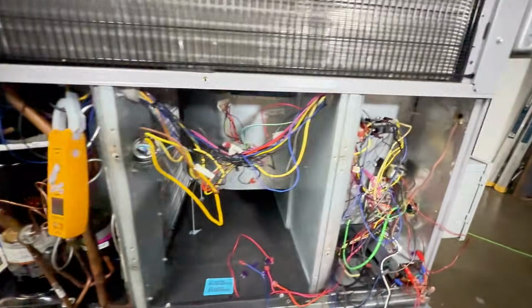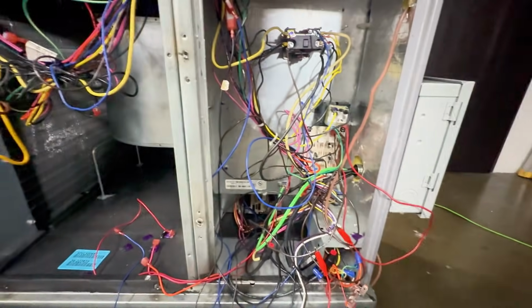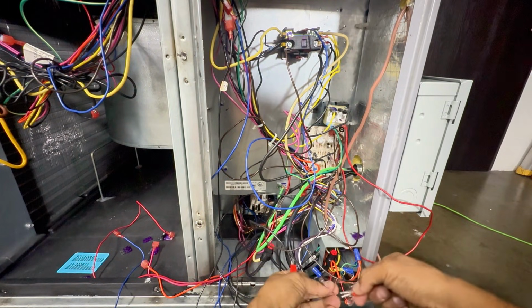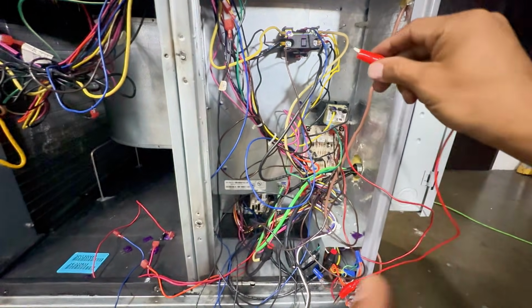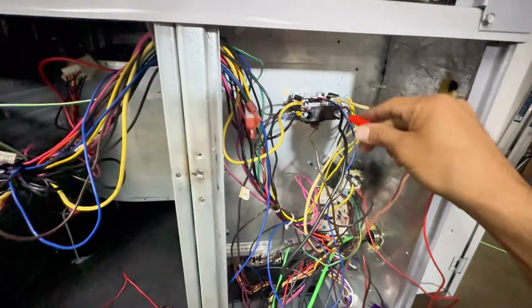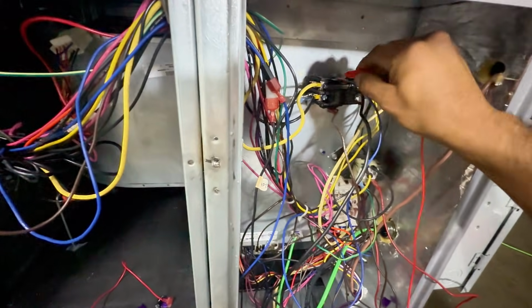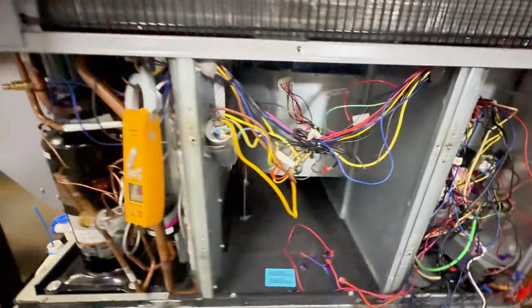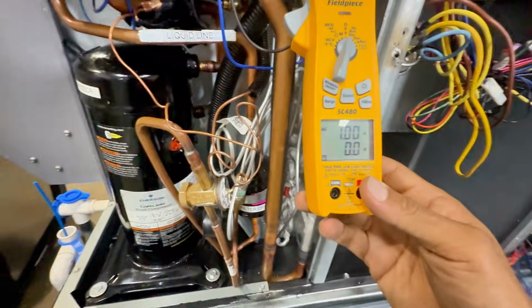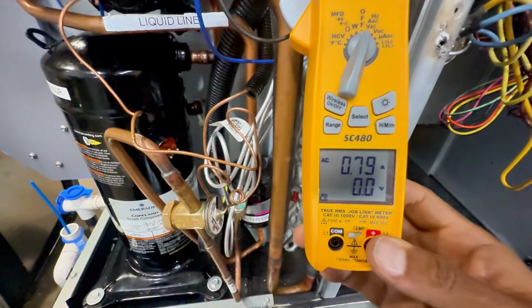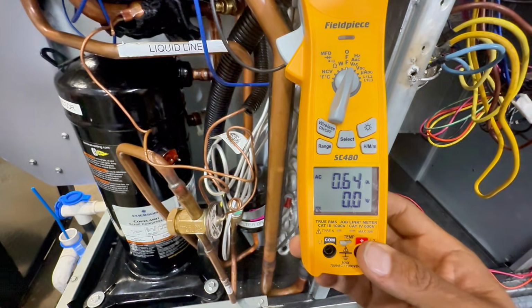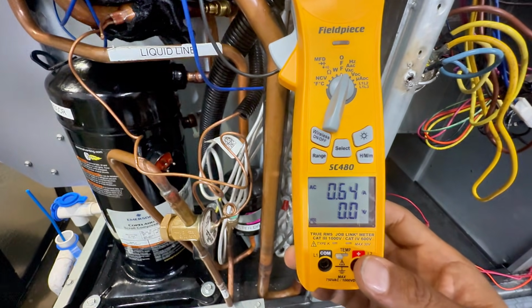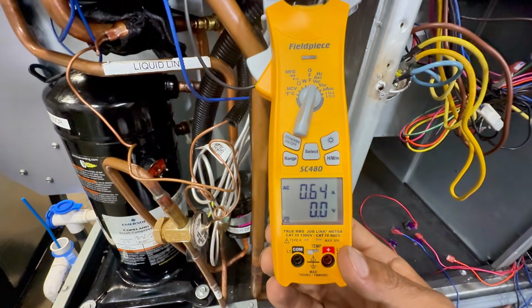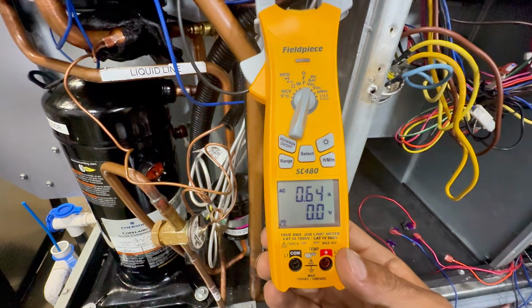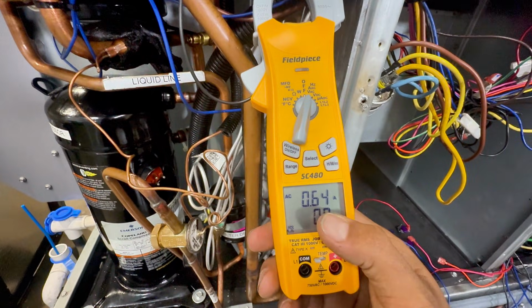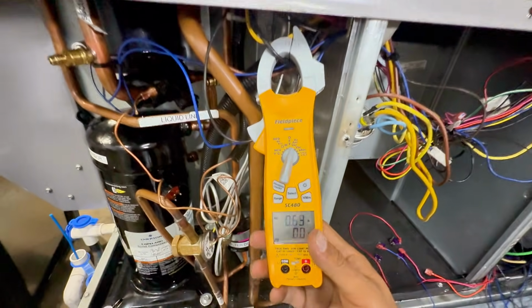And then let's see how much we're pulling. So I'm gonna do the same thing I did earlier, but I'm gonna get straight 24 volts, and I'm just gonna power up that contactor because the power for the condenser is coming essentially from the contactor here. So let's go ahead and, okay. Let's give it a second. Okay, you see, it did kind of go up, but then it came down to 0.6. There you go, 0.64. It's pulling right under the full load amps, right? It told me up there 0.64, and look at that, 0.63, 0.64. Awesome. And I'm checking it on the common.